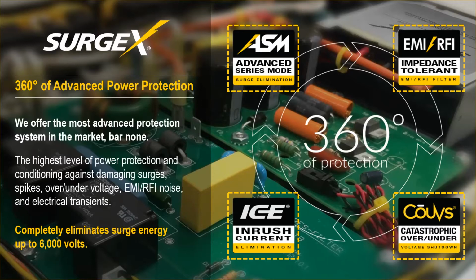Everyone else is a surge suppression device; we're a surge elimination device. We have videos and other collateral that goes more in depth, but in a nutshell, advanced series mode works similar to noise canceling headphones: we look at the waveform coming in, and if we see any surge energy, we create an equal yet opposite surge inside what we call the reactor. We use an additive process, so adding the original signal to the equal yet opposite signal cancels just the high frequency surge out of it, eliminating the surge without turning off the product — it just lets it go through. It's very unique technology.